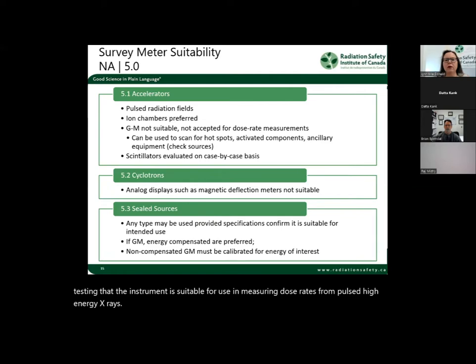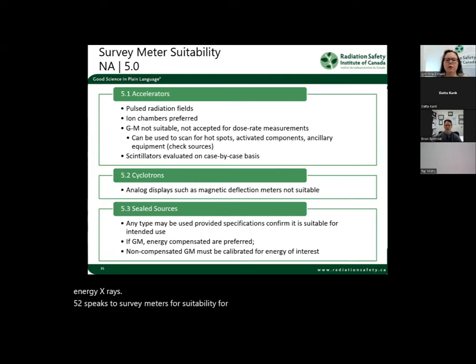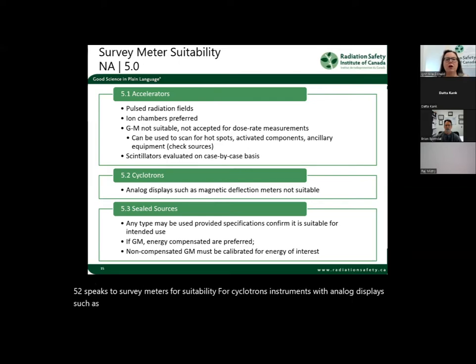5.2 speaks to survey meters for suitability for cyclotrons. Instruments with analog displays, such as magnetic deflection meters, are not suitable for use in strong magnetic fields present in the immediate vicinity of cyclotrons.